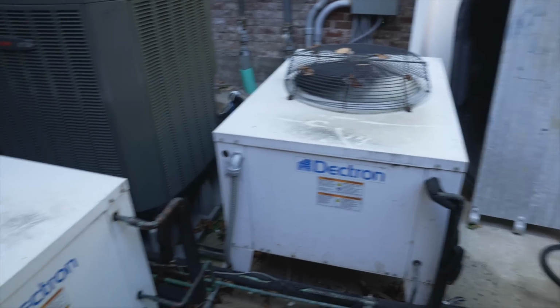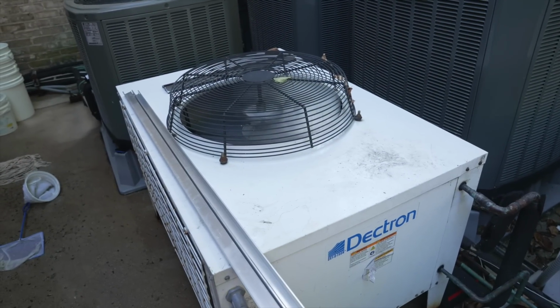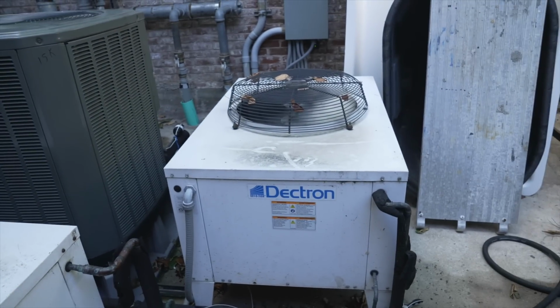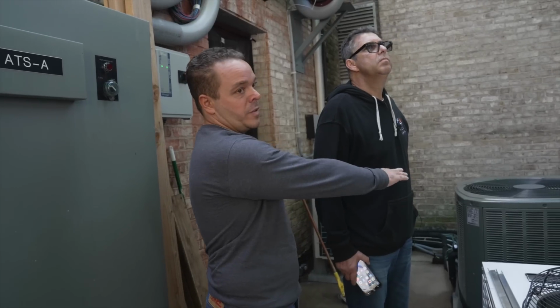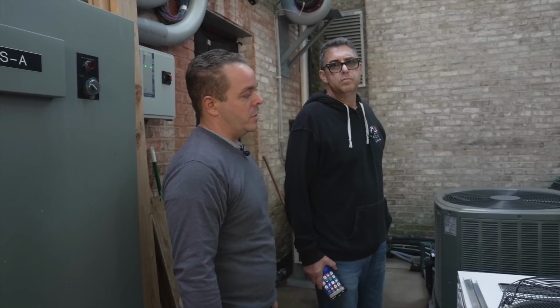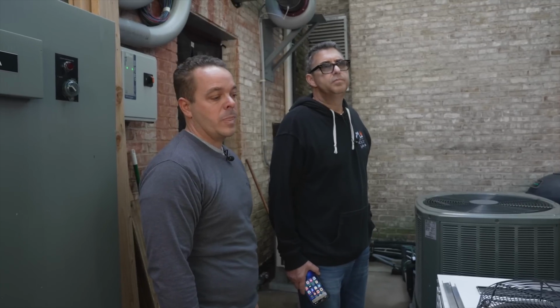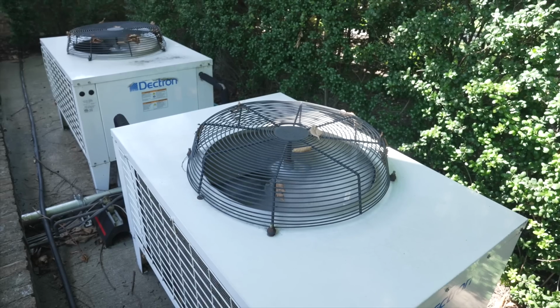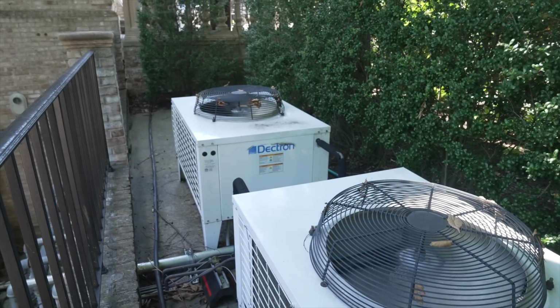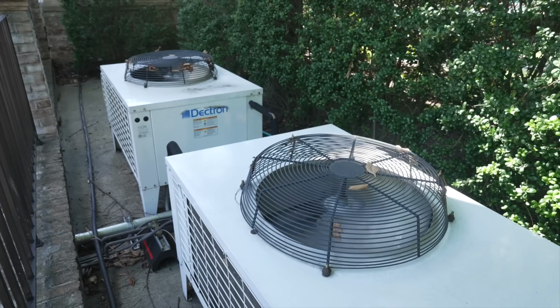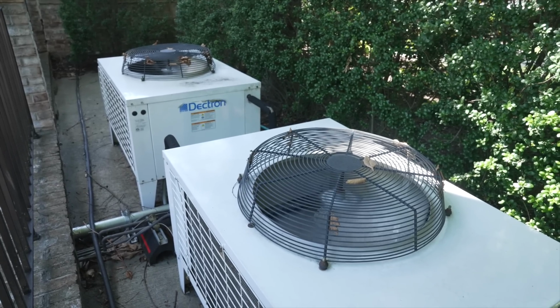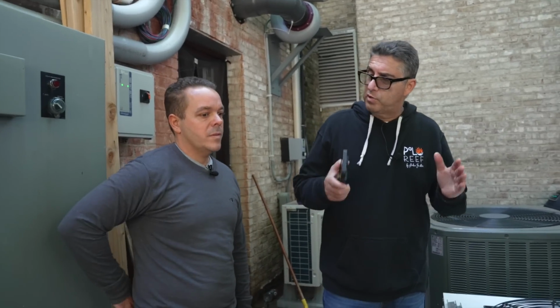And then the other equipment in this area, the 2 bigger units here are the 2 5-ton condensers for the closed loop chillers. And the smaller one here is a 4-ton condenser for the chiller on the 2,500 closed loop. On the top of the pit here, we have 2 more Dectron units, which are for different dehumidification in different areas of the house. Tell us a little bit about why we did 2 on closed loop, 2 on the regulars, and the redundancy.